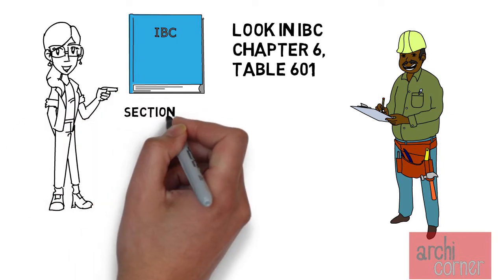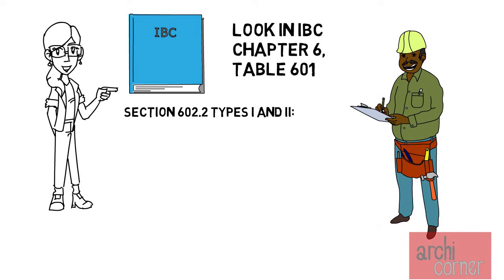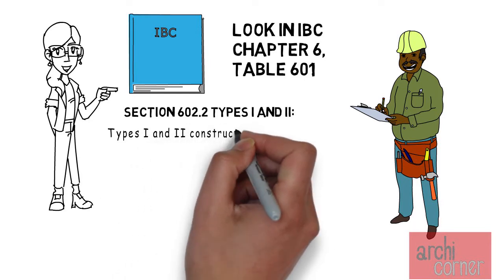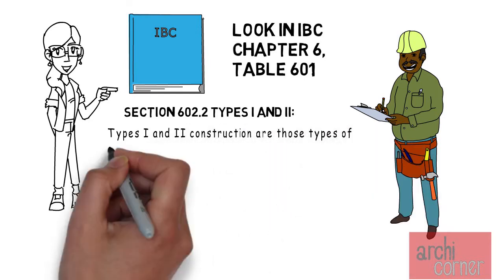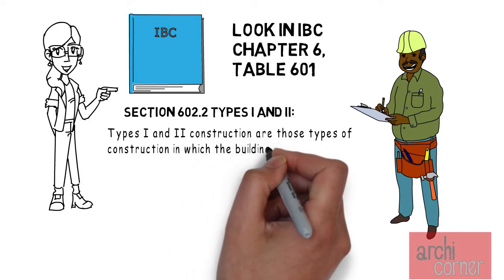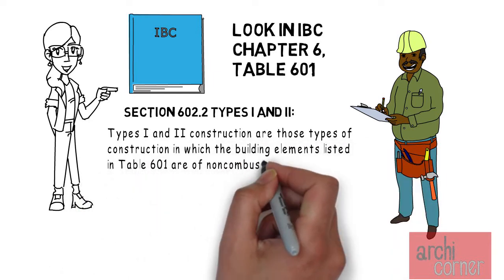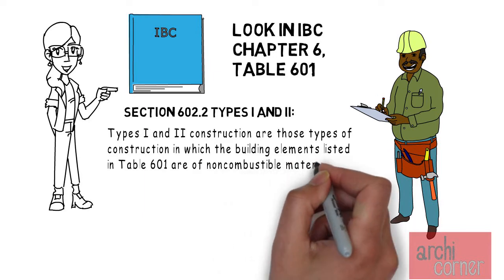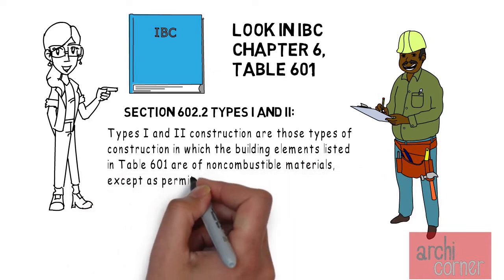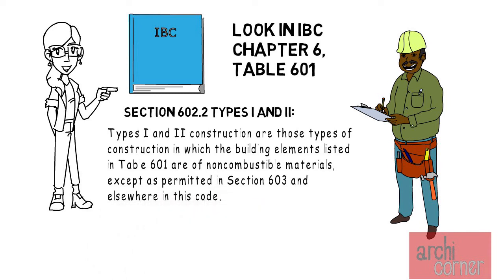If you look at section 602.2 you will find something interesting. Type 1 and type 2 construction have the same exact requirement when it comes to specific building elements. This section states that type 1 and 2 construction are those types of construction in which the building elements listed in table 601 are of non-combustible materials, except as permitted in section 603 and elsewhere in this code.